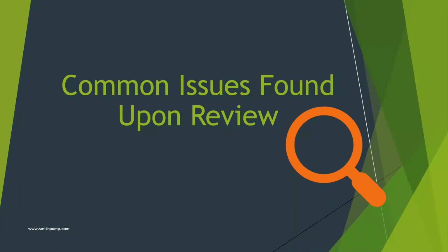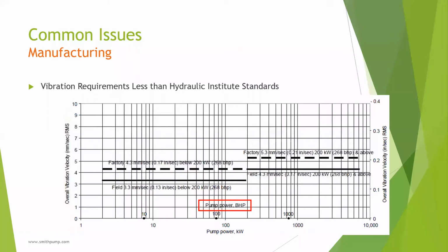And let's jump into more common things we find when reviewing a vertical turbine spec. Sometimes we see requests for field vibration to be less than Hydraulic Institute published values. Almost any vibration level can be achieved in the field. The cost to hit that may be substantial. All manufacturers design their equipment to meet current HI vibration levels. Some manufacturers will not bid the jobs if asked for vibration levels less than HI. Others will bid at a premium price to cover themselves.